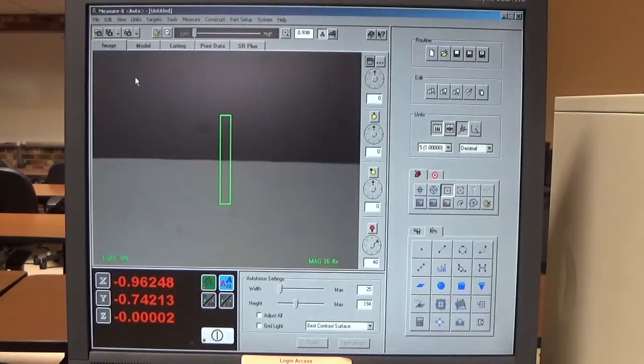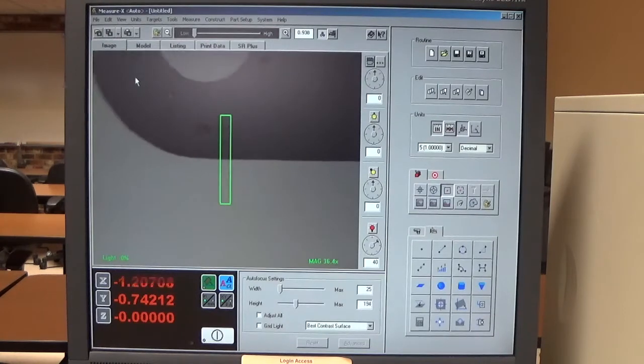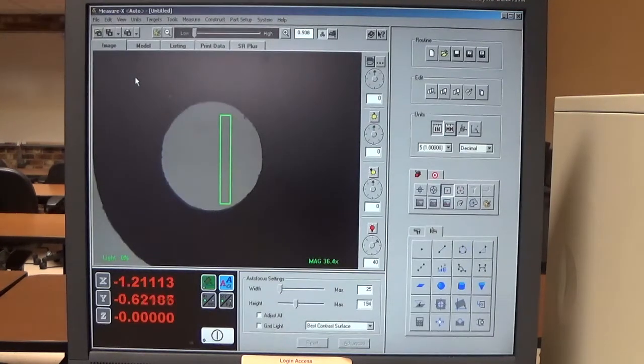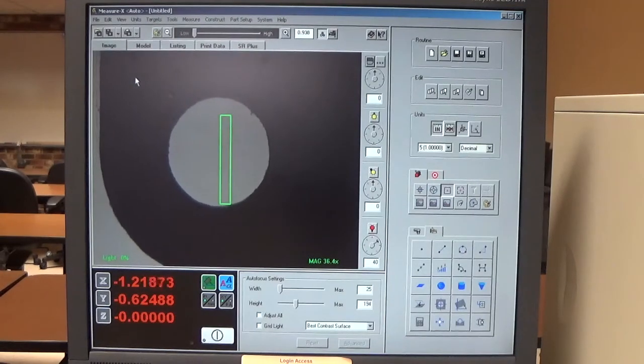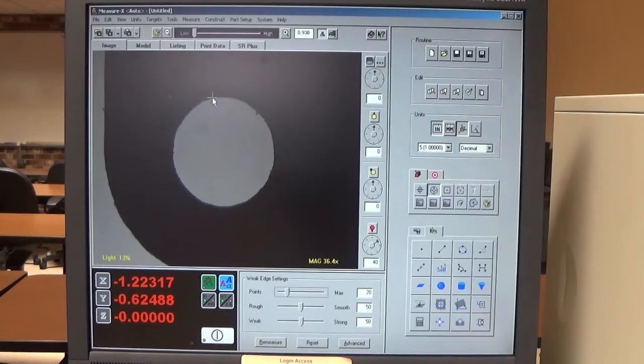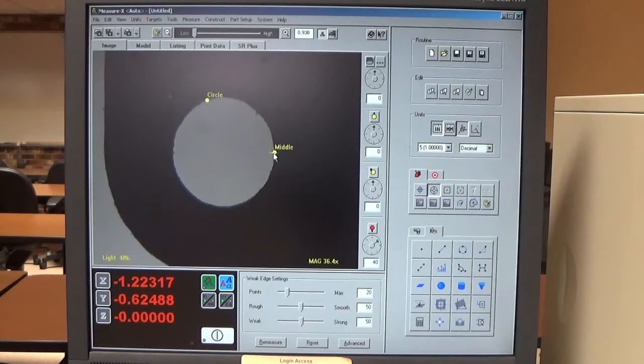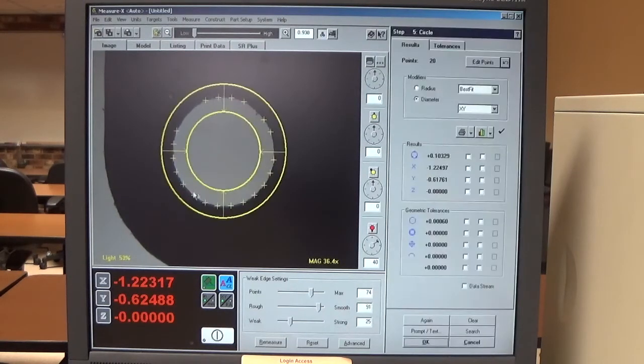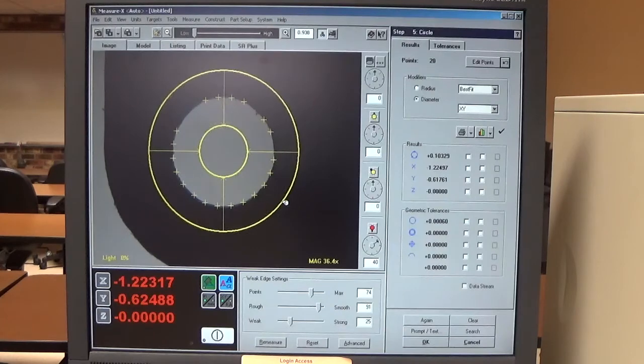Next we're going to go over some basic measurement functions — typically we're going to measure diameters and edges. I'm going to measure this diameter. I position the feature in the center of the window, go to my toolbox, and select the feature finder. A crosshair shows up by my mouse pointer. I click on the edge of the surface, measure it as a circle by selecting three points, size it, remeasure, and click OK.